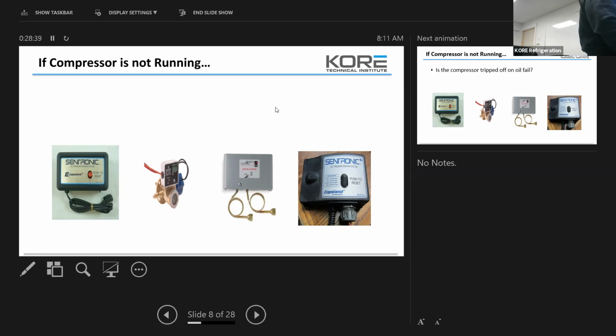Okay. So that's what all of these different controllers are; you might run into any one of them. You need to understand that if you're tripped off on oil, probably, in my opinion, it's the one thing that kicks everybody's butt. When you're dealing with oil issues, you usually have to go through a few steps. A lot of times some steps are missed or some steps don't want to be taken, because digging into an oil system is usually a lot of work and a lot of time to diagnose the issue, and it can come and go. It's sporadic. You can hit that red button and stand there for 2 hours and nothing happens, right? Then you go home, and at 2 a.m. they call you back out because the store's warming up.